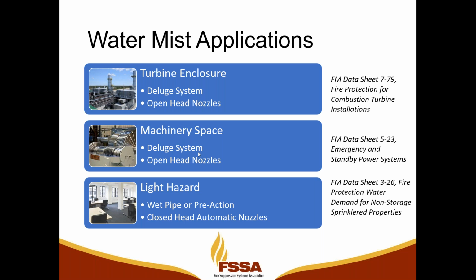What these spaces have in common is that we've got hydrocarbon fuel flowing through a system doing a job. So it could be a diesel generator, it could be a gearbox that's got lube oil supplied to it, it could be a bearing and shaft situation that's being lubricated, it could be the lubricating skid that's next to or underneath one of these other hazards. And so these types of hazards are subject to spray fires, pool fires, and that kind of thing.